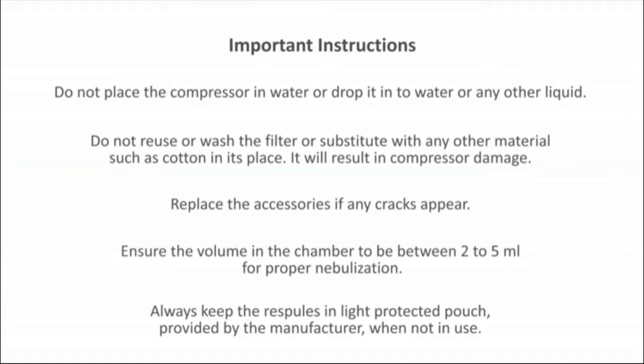Replace the accessories if any cracks appear. Ensure the volume in the chamber is between 2 to 5 mL for proper nebulization. Always keep the respules in the light-protected pouch provided by the manufacturer when not in use.